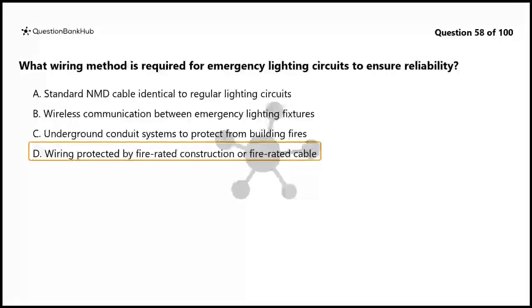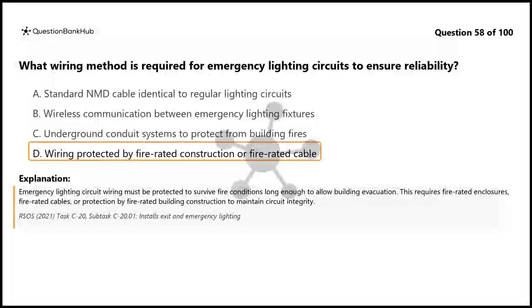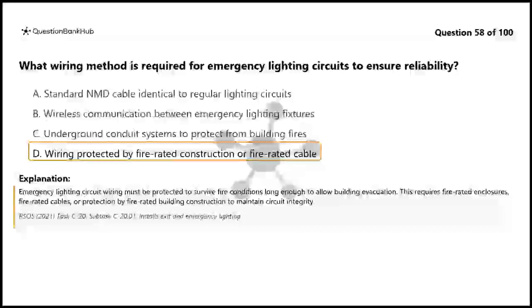The correct answer is D. Wiring protected by fire-rated construction or fire-rated cable. Emergency lighting circuit wiring must be protected to survive fire conditions long enough to allow building evacuation. This requires fire-rated enclosures, fire-rated cables, or protection by fire-rated building construction to maintain circuit integrity.